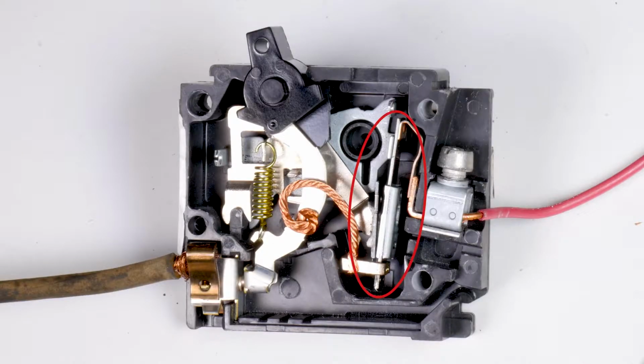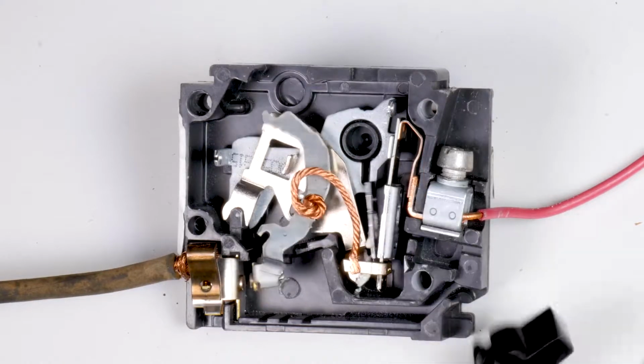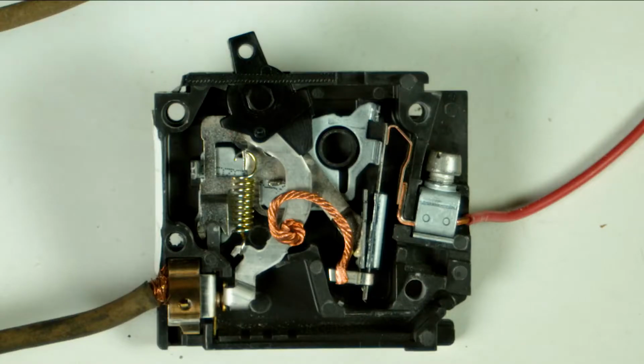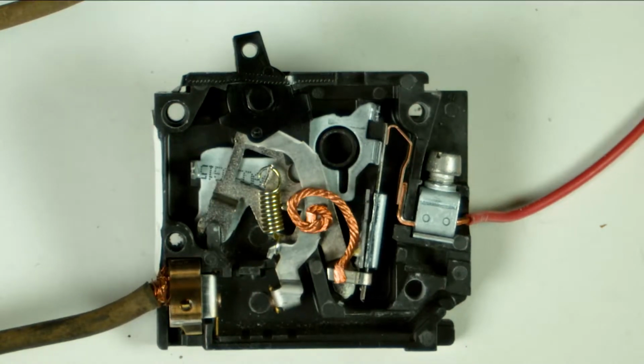After watching the overload and the short circuit scenarios, the one thing I noticed is that this particular breaker, which is the most common household type, seems to be thermomagnetic. What that means is they've combined two mechanisms in one: a thermal overload for gradual overcurrent situations, and a magnetic device for situations that need to be interrupted immediately.